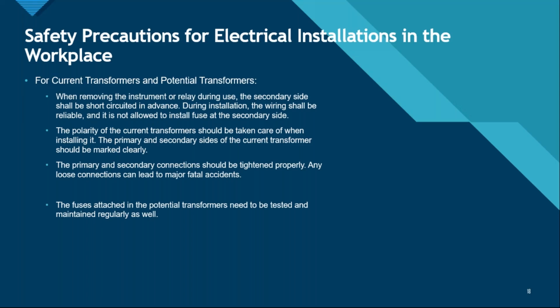The fuses attached to the potential transformers need to be tested and maintained regularly as well. For the potential transformers or voltage transformers, there are big size fuses connected on the top of the potential transformer. So when there is regular maintenance going on for an electrical panel, those fuses of the potential transformer also need to be cleaned for any carbon that might be there on the fuse before installing them back.